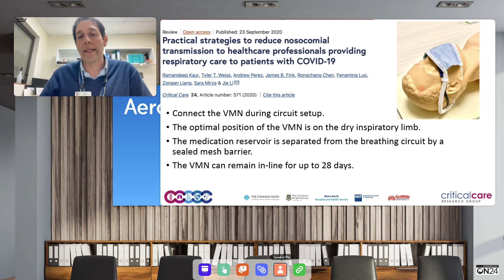And when I use high flow, I usually connect the vibrating mesh nebulizer already during circuit setup, and this is very important in order to not disconnect anything afterward. I put the vibrating mesh nebulizer on the dry inspiratory limb, and the nebulizer can remain in line for up to 28 days. So there are no problems at all with disconnecting the line.